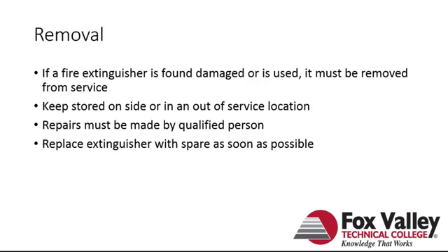If you do have to remove a fire extinguisher from use, either because it's damaged or used, you want to make sure you remove it, obviously. You either want to keep it stored on its side or in an out-of-service location. You want it marked, that way other people aren't grabbing it to go use a fire extinguisher. And you do have to have repairs made by a qualified person. This probably isn't something you're going to do within your own facility. It's probably something you're going to have a contractor come in to do. And then you want to replace that extinguisher as soon as possible.